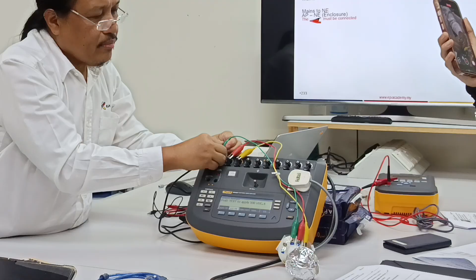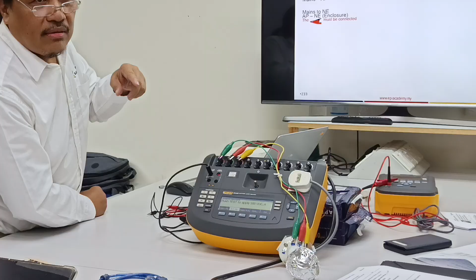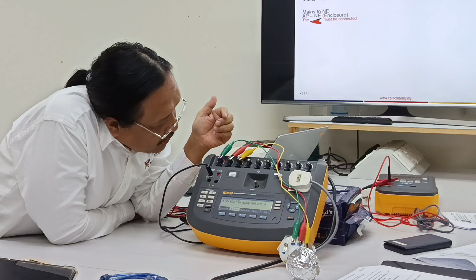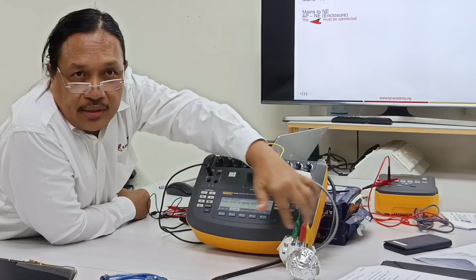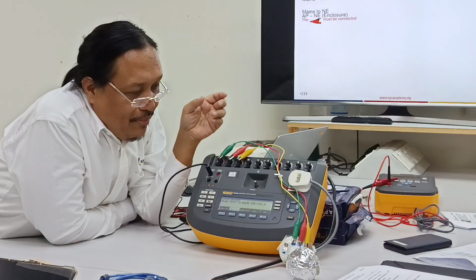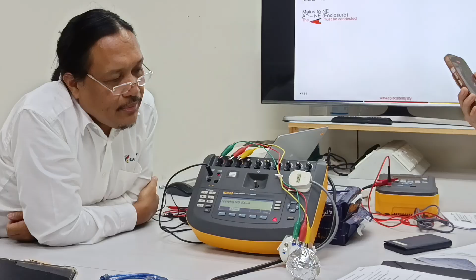No need to follow the correct order for this parameter, insulation resistance. For leakage current, follow the correct order. What do you mean by order? Order means if it's right arm, should be right arm from here on the machine. RA. LL should be LL from the machine. This is insulation resistance, don't care about it. Because this analyzer will just connect them all together. So what's the point of following? For isolation only. So just select that one, press test.